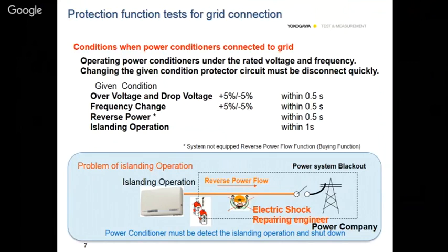Protection function for the grid connectivity. When power conditioners are connected to the grid and operating under the rated voltage and frequency, if the given condition changes, the protection circuit must be disconnected quickly. When there is over voltage or a voltage drop, if the voltage goes below or above the nominal by 5%, it should disconnect. Frequency change is again plus or minus 5%, and reverse power flow as well. Everything should happen within 500 milliseconds, less than 0.5 second.